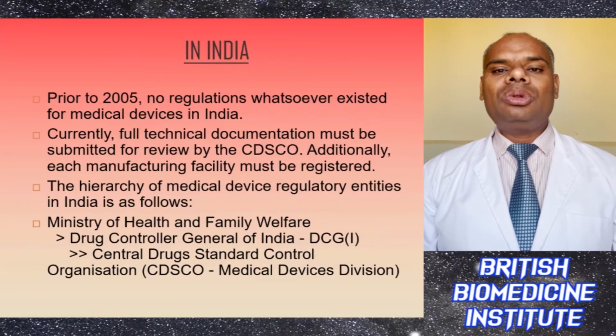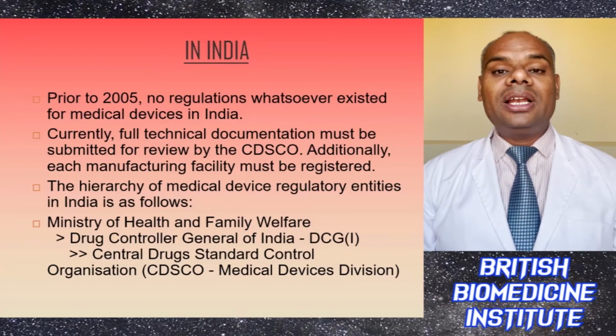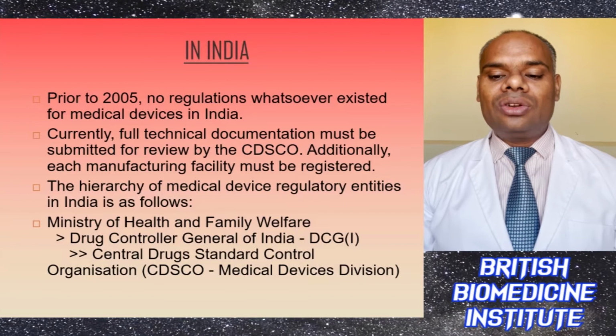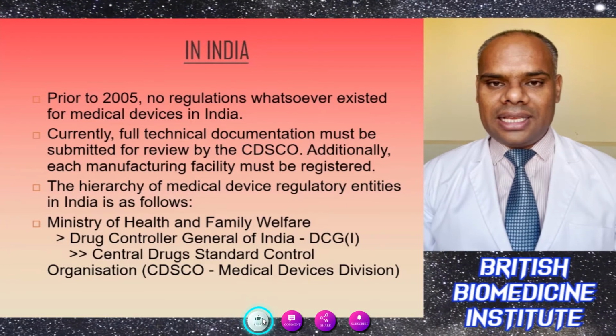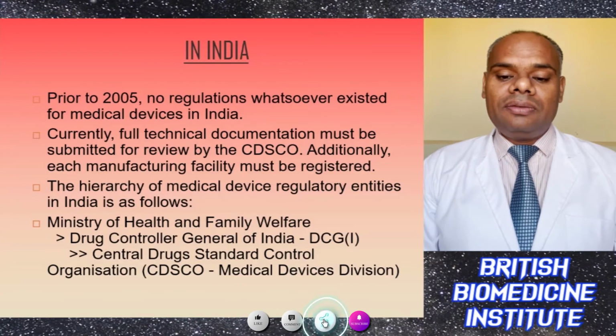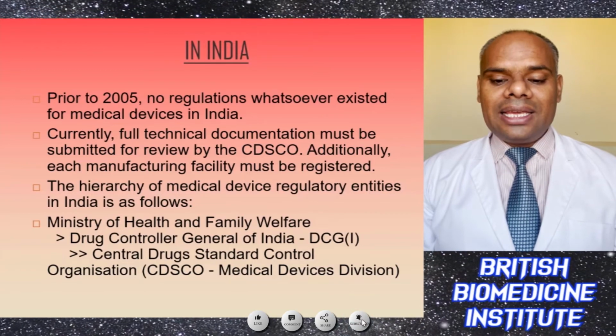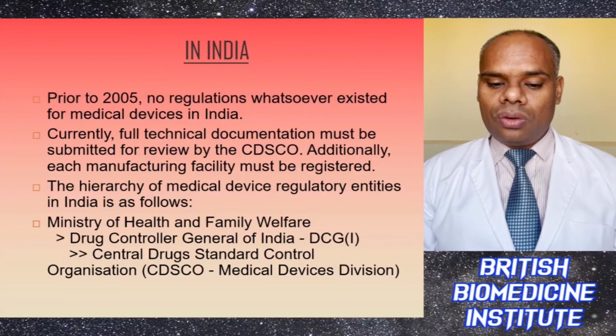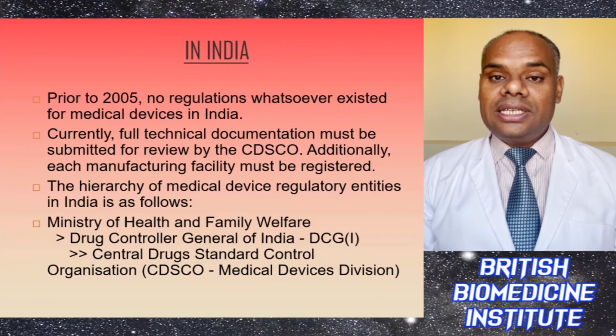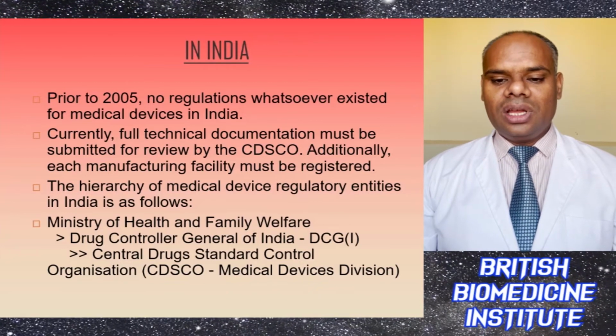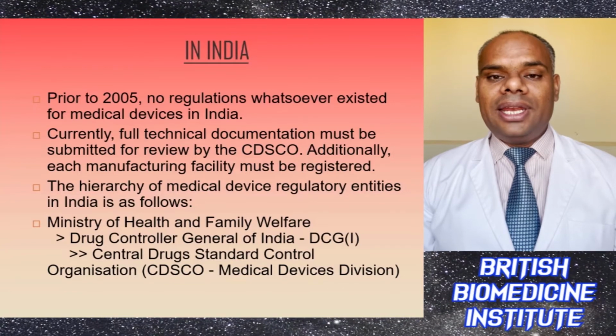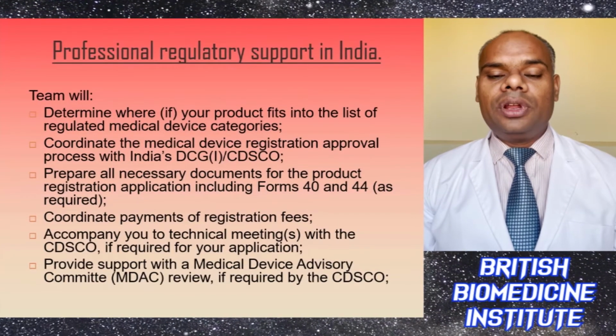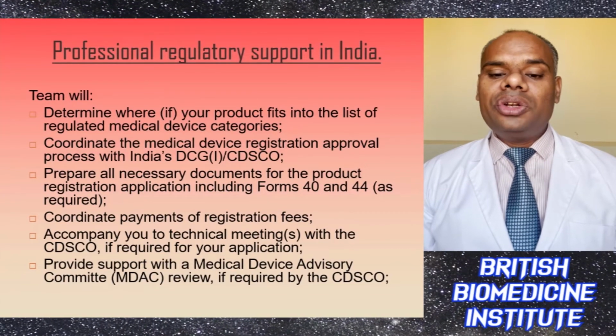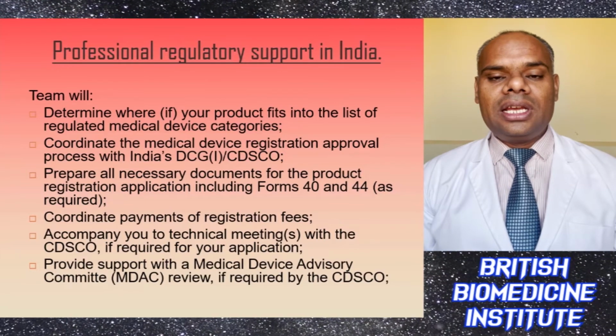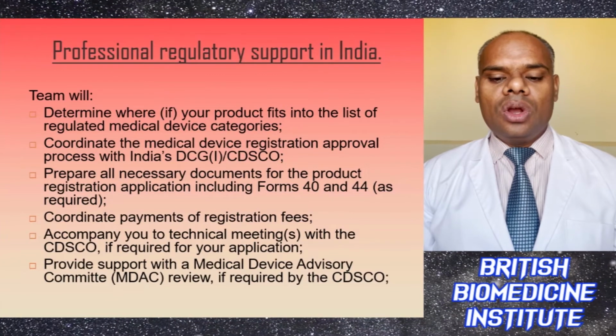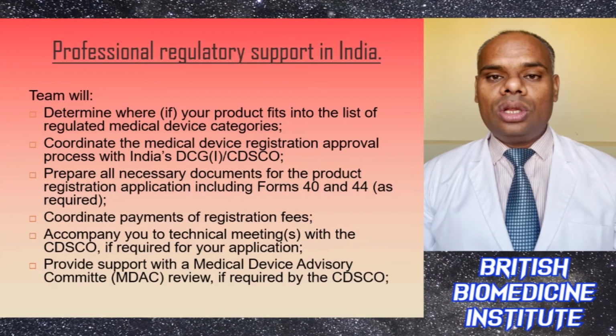In India, prior to 2005, no regulations whatsoever existed for medical devices. Currently, full technical documentation must be submitted for review to the CDSCO, and additionally, each manufacturing facility must be registered. The hierarchy of medical device regulatory entities in India is as follows: Ministry of Health and Family Welfare, DCGI, CDSCO. So the team will help in determining if the product fits in the list of regulated medical device categories. They will coordinate the medical device registration approval process in India with the DCGI or CDSCO, and prepare all necessary documents for the product registration application, including Form 40 and 44.